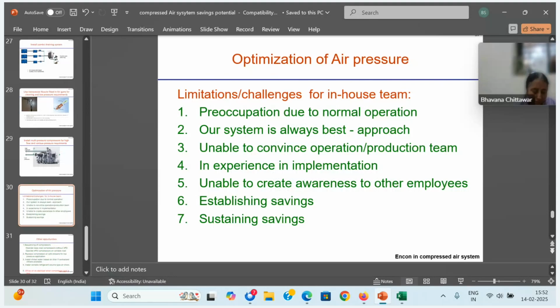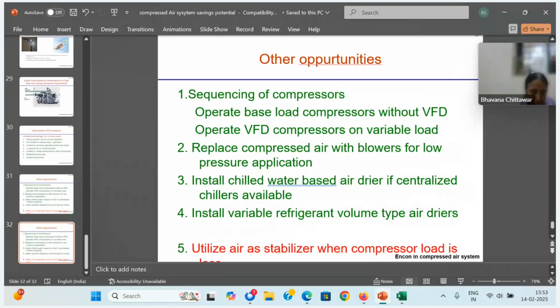I'll go through these slides quickly. There are other approaches available. Sequence of compressors: operate the base load compressor without VFD, and operate with VFD on variable load. Always go for a VFD compressor of smaller capacity. Don't go for VFD on higher capacity compressors. Even if you want to buy a VFD compressor, go for one standard compressor and one small VFD compressor. The higher capacity compressor works for base load, the small capacity one with variable load. This will save a lot. The investment will be the same, the same cost, and you will get 2 compressors. Your payback will be less than 6 or 7 months.